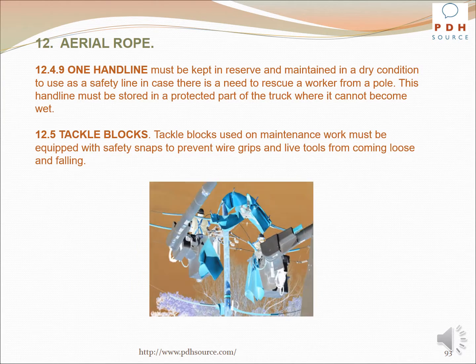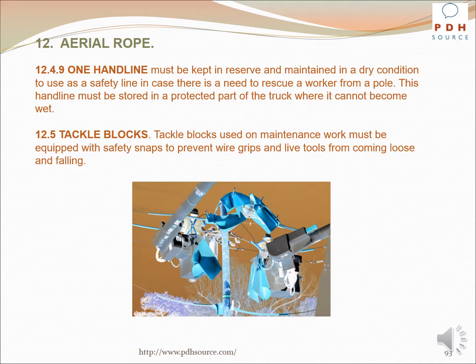One hand line must be kept in reserve and maintained in a dry condition to use as a safety line in case there is a need to rescue a worker from a pole. This hand line must be stored in a protected part of the truck where it cannot become wet. Tackle blocks used on maintenance work must be equipped with safety snaps to prevent wire grips and live tools from coming loose and falling.